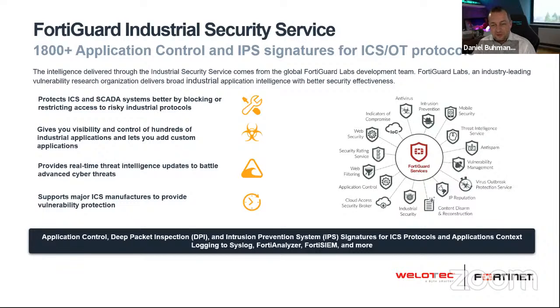So you can protect all your ICS and SCADA environments. You can see what's going on - you don't have to use it just for blocking, you can use it for understanding. When you see in the firewall that two devices are talking on IEC 104 or 61850 or whatever protocol is used, or if you want to create firewall policies for OPC - which is really difficult because OPC uses a different port for each message sent through TCP/IP - you can use these things to better understand and secure your network.